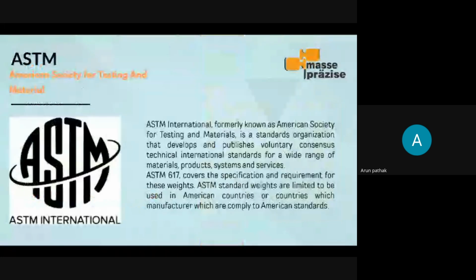Second one is the ASTM standard. American Society for Testing and Materials, or ASTM, is an American standard forming body for a wide range of materials, products, systems, and services. For ASTM weights, ASTM E617 is the number of the standard. ASTM E617 covers all technical aspects of the weights, just like OIML R111 does for OIML weights.